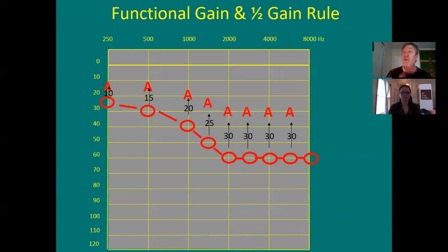And what you did was retest the guy's thresholds in a sound field. So first you tested the guy under headphones, you got the hearing loss. Take off the headphones, put a hearing aid in, turn it up to a comfortable volume, set the person 1 yard away from a speaker, and play warble tones.